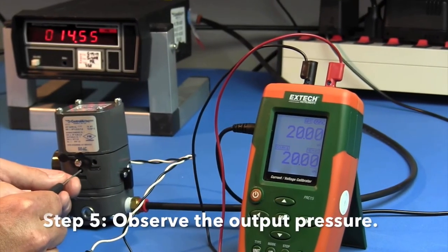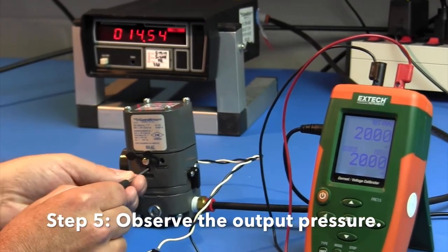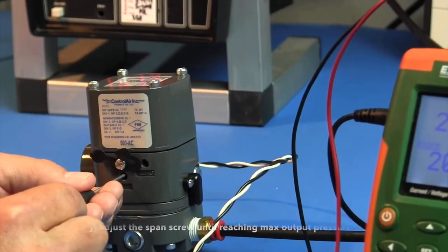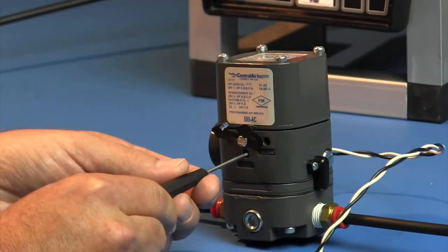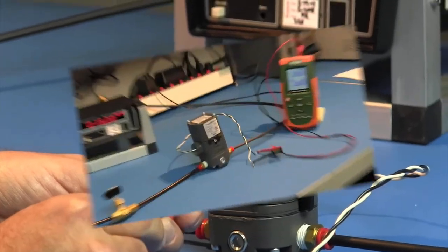Step 5. Observe the output pressure. If necessary, adjust the span screw until reaching maximum output pressure setting. Turn span screw counterclockwise to increase pressure, clockwise to decrease pressure.